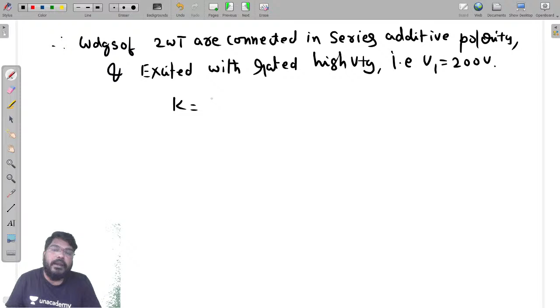When V1 is equal to 200 volts, K is equal to how much? K is 200 divided by 300, which is equal to 0.66. Now calculate the kVA rating of the auto transformer, that is 1 by (1 minus K) times the kVA rating of the two-winding transformer. Calculate it yourself.